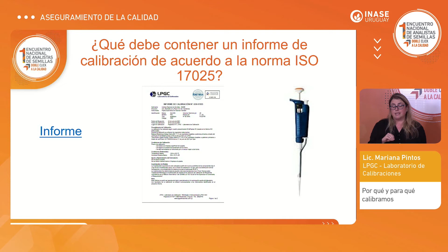method, traceability, metrological traceability. So it has to be included what was the pattern that was followed, the metrological uncertainties, and if it's necessary to adjust the instrument, you have to show the previous values and then the values after adjusting it and the things associated to the result. So there are more points, but this would be the most important ones. As I was referring, one of the things that it requires is traceability, metrological traceability. What do we understand by metrological traceability?